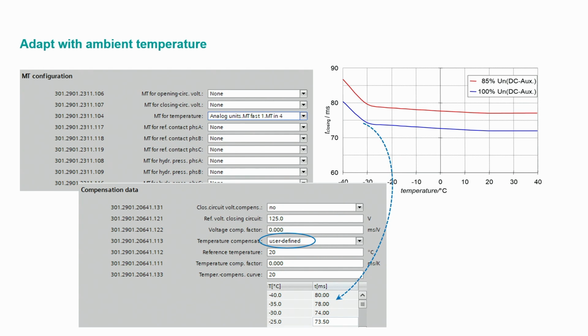If compensation of the closing time due to ambient temperature is required, this is optional, and can be implemented with a temperature sensor connected to a transducer input. Configuration of the temperature compensation is as shown by selection of the corresponding transducer top left diagram. A linear, or as in this case user-defined compensation, can be selected as shown in the bottom diagram. For the user-defined compensation, setting points from the curve on the right-hand side can be entered.